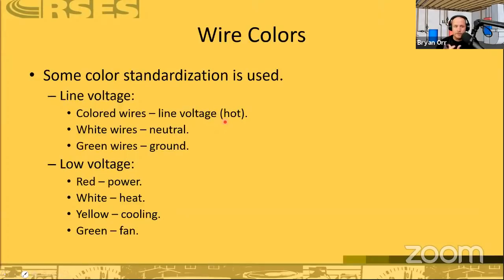If you're ever working with two conductor wire where you're using a white wire as a current carrying conductor, you need to make sure you phase tape it well up the wire. Now again, this is an electrical thing, and I'm not teaching electrical code here, just identification. People, when they visually see white, will assume it's a neutral. So if a white is not being used as a neutral and is instead a true hot current carrying conductor, you should phase tape it up the wire with black or red tape. The codes have recently changed about that too, so I'm not telling you current NEC code, just a good best practice.